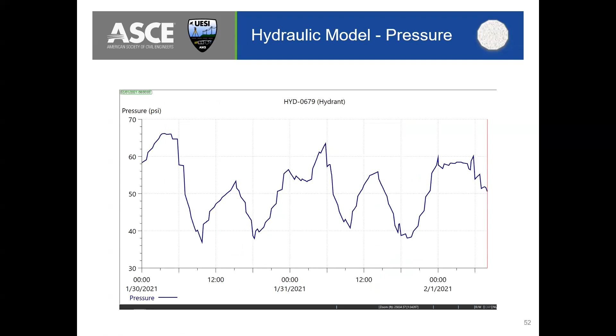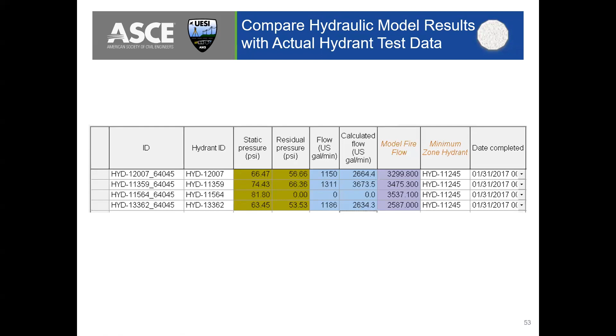So here we've got from a hydrant test at 20 PSI, we're saying 2600. The model fire flow is indicating around 2600. That's really good. We can see here that we got absolutely no flow, no residual pressure, and we're expecting fire flow of 3500. So that'd be one you would go investigate. So always good to compare model data with real data collected in the field, especially in the calibration process. So once you have a model, you can look at existing fire flow.